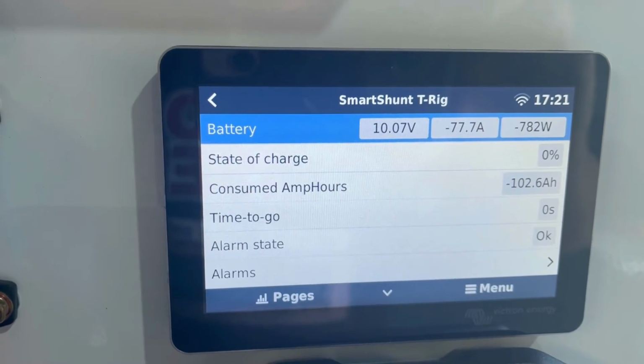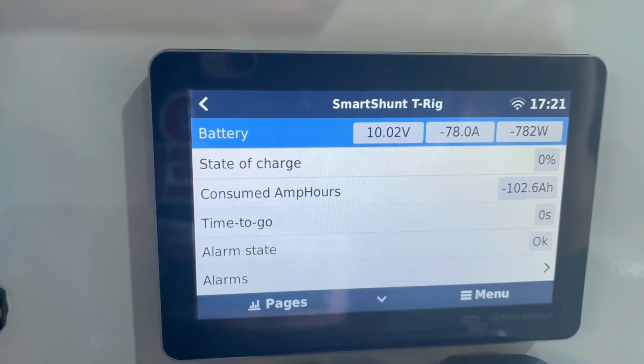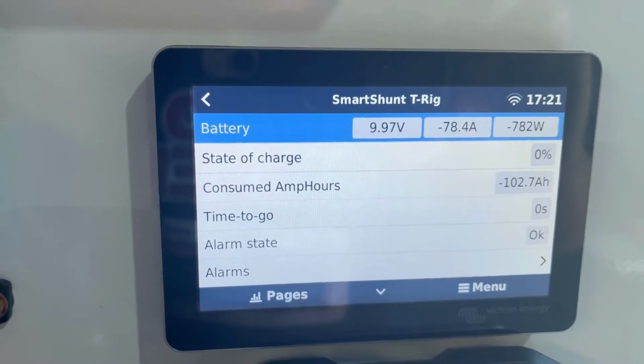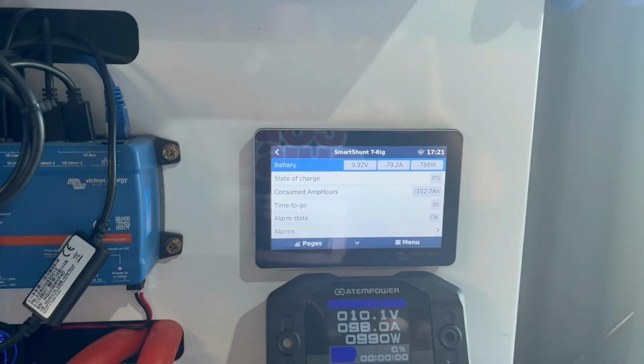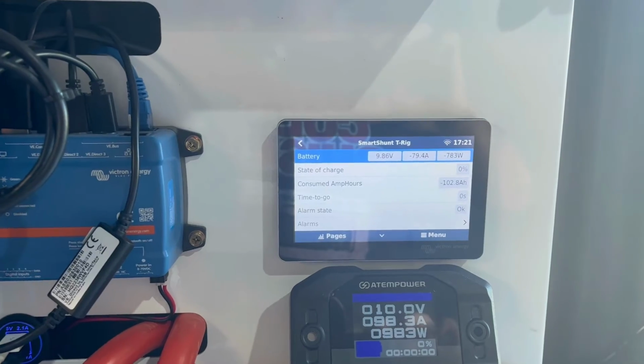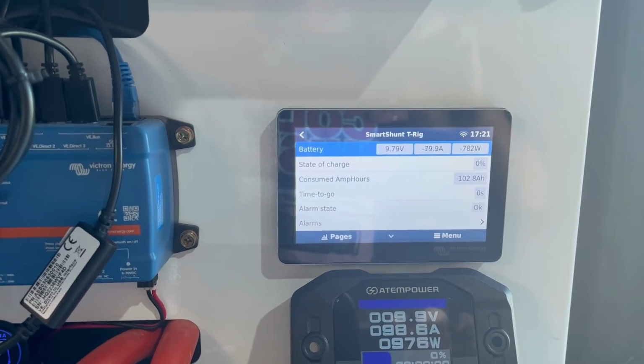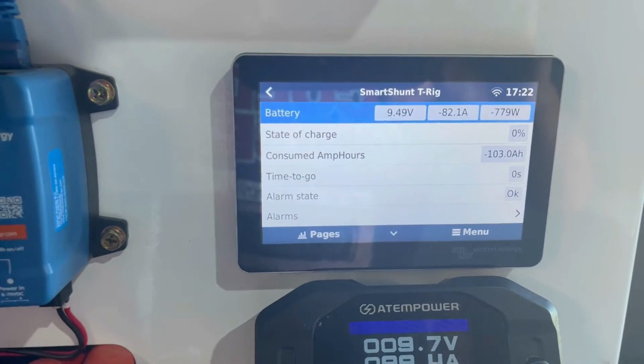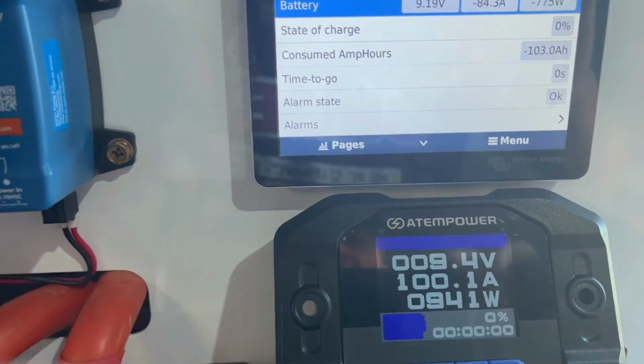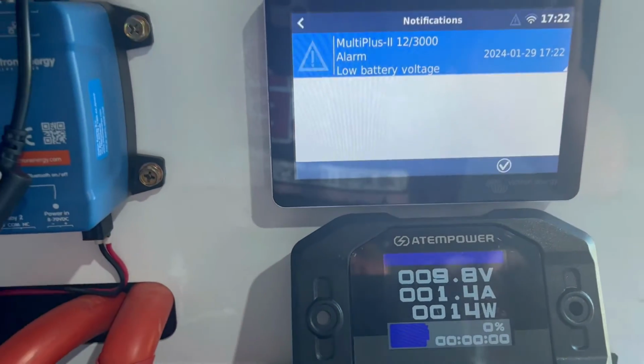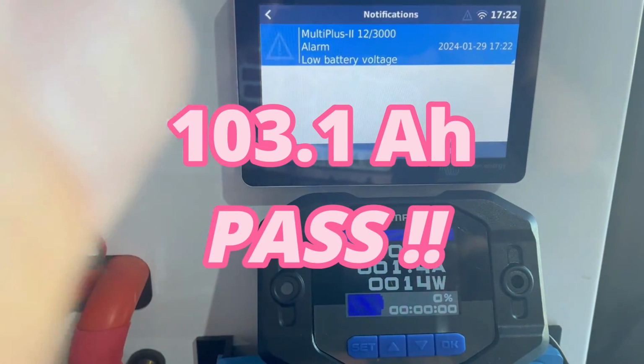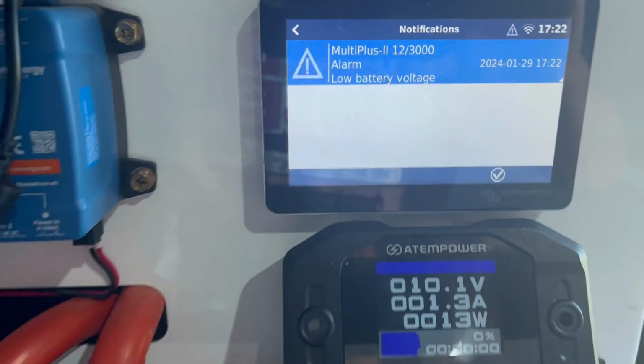Okay, getting close now, guys. Okay, so the low voltage alarm on the inverter's now come on, and you can see it flashing here. So the inverter may trip before the BMS again, which I don't like. This thing should have cut out by now, and there we go. So the inverter cut off before the BMS did.